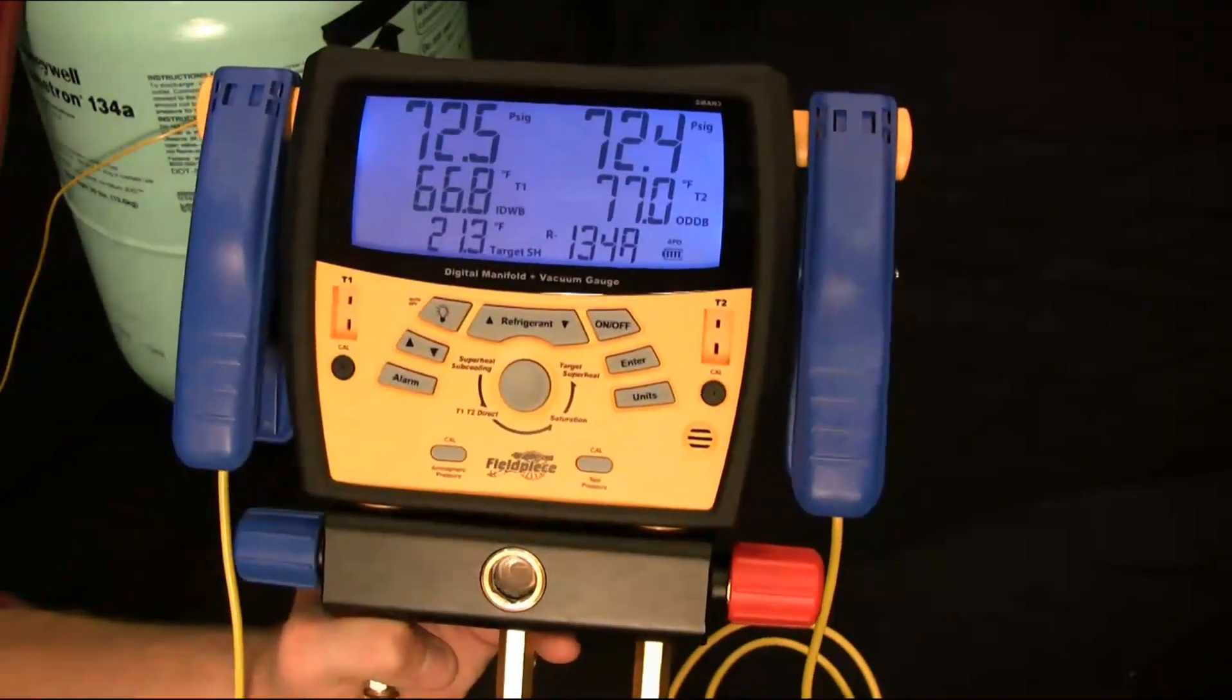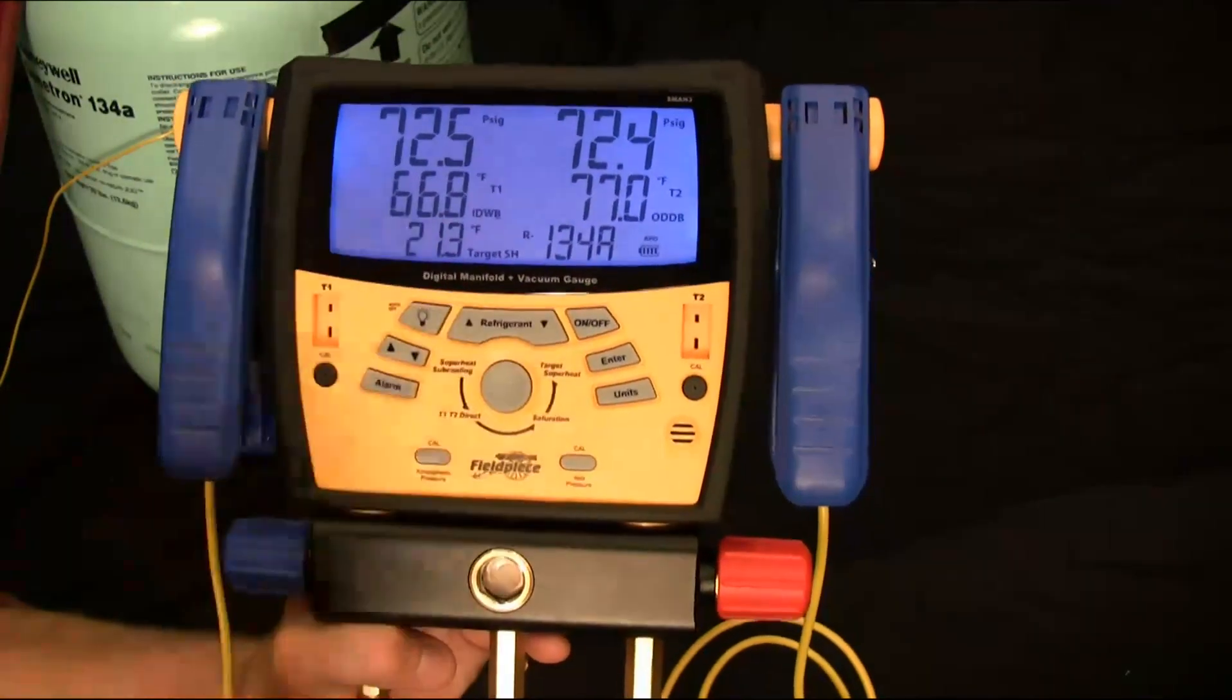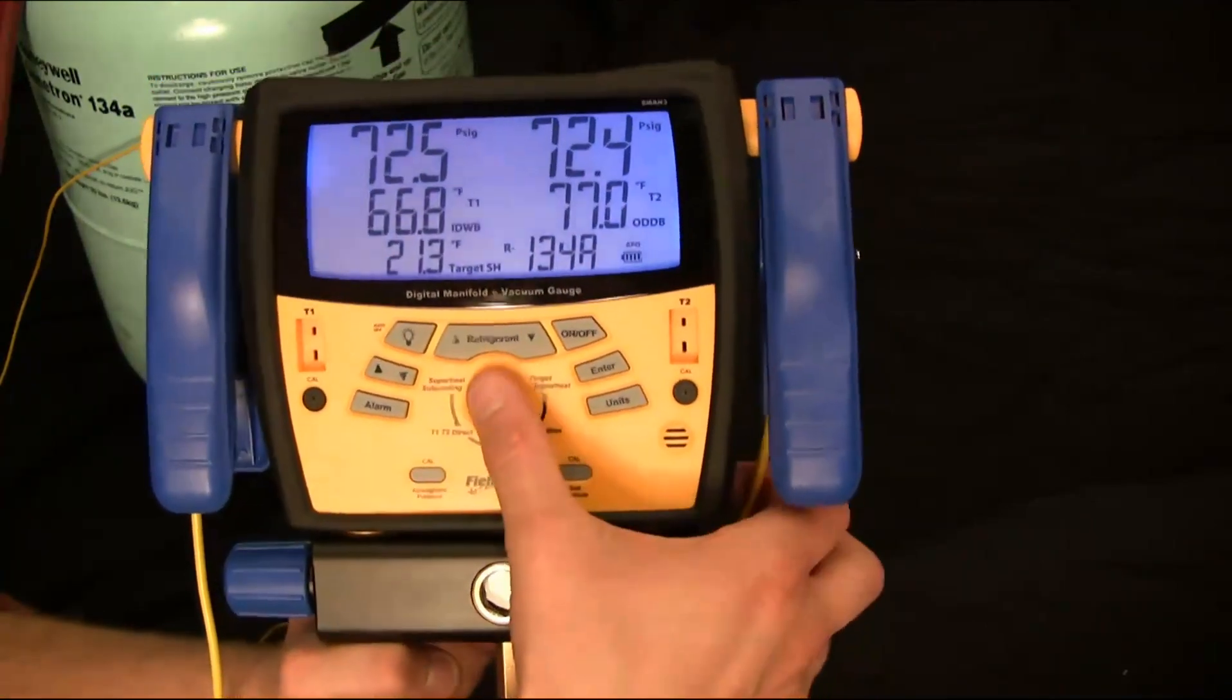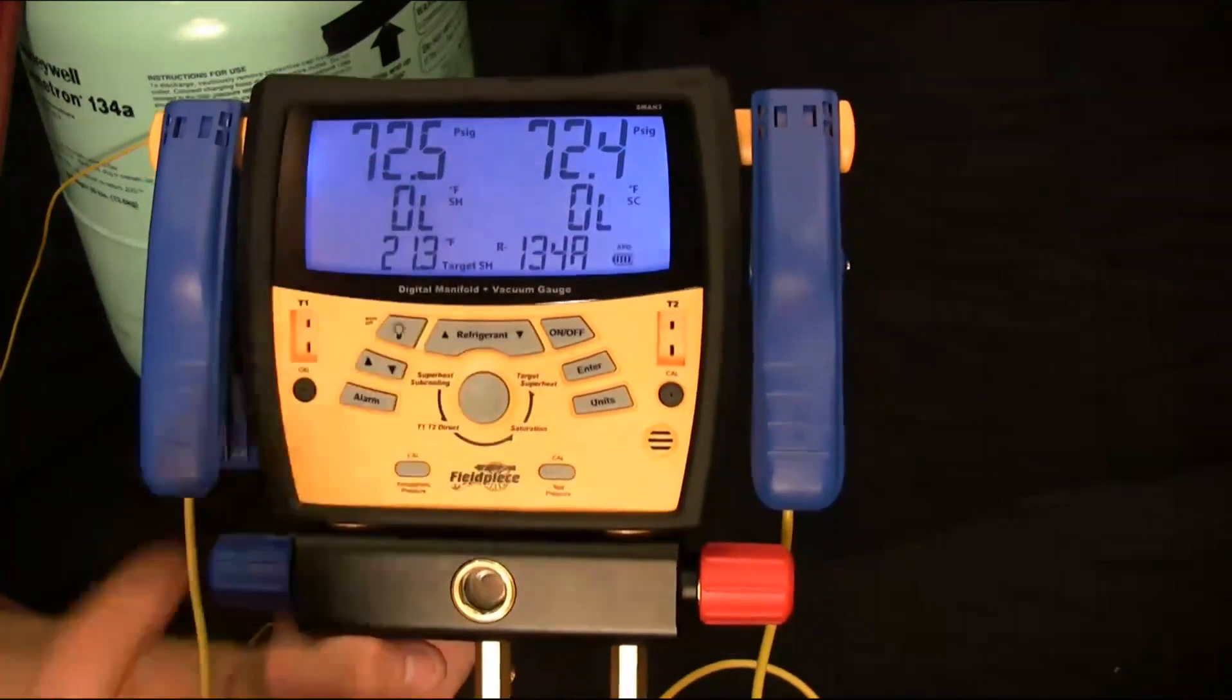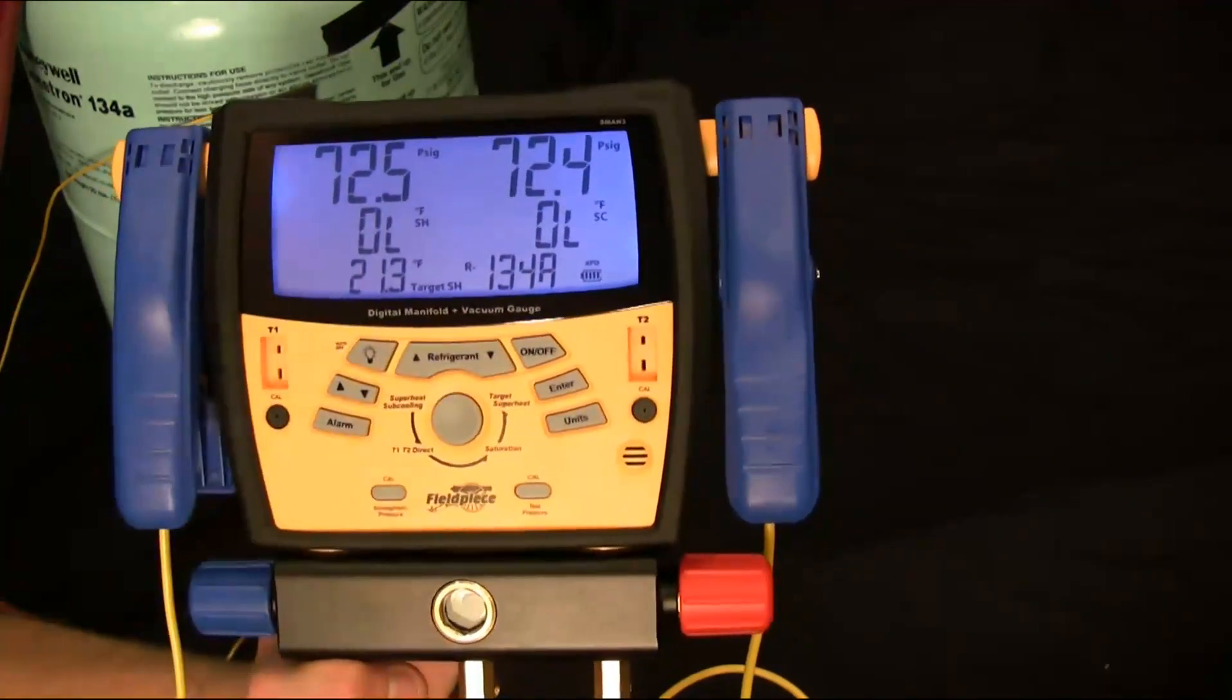And I'm going to enter that in, just go through all the digits and press enter. Then it'll calculate my target superheat right here. So if I have these indoor wet bulb conditions and outdoor dry bulb conditions, my target superheat should be 21.3 degrees. So then what you can do is go to the superheat and subcooling mode and directly measure your superheat and see if you're within range. And it's going to label both your target superheat and your actual superheat. And that way you can dial in fixed restrictor systems.